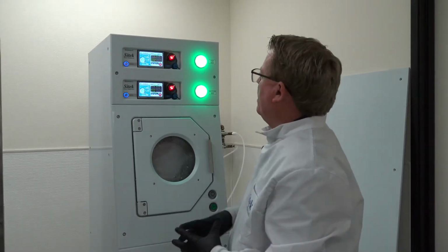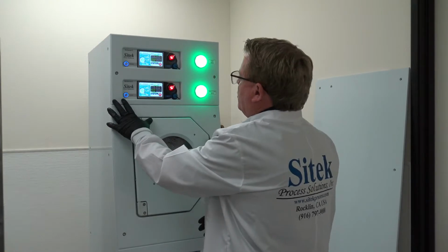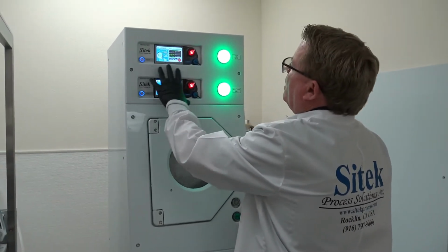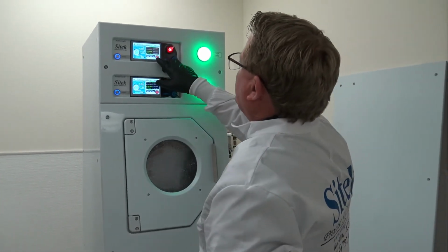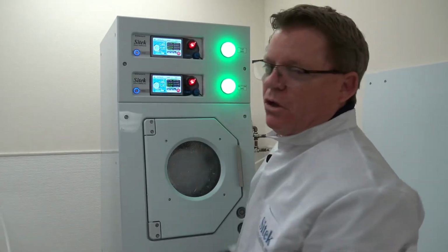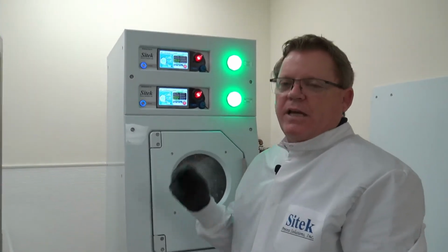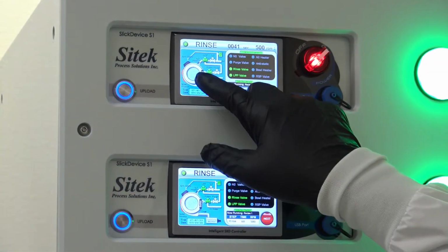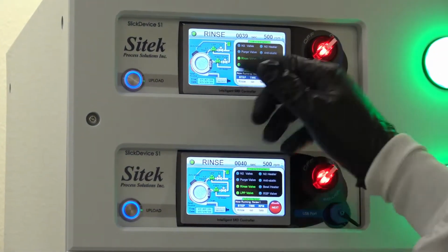Okay, so we're in the rinse cycle. What I'll show you is, because the Slick Device is running, when you're in a step, green means on. So right there you have your LPP, which is low pressure purge - that's a low pressure N2 purge into the bowl. And then you have the rinse valve. Both are on, and you can see in the graphical display the water spraying.